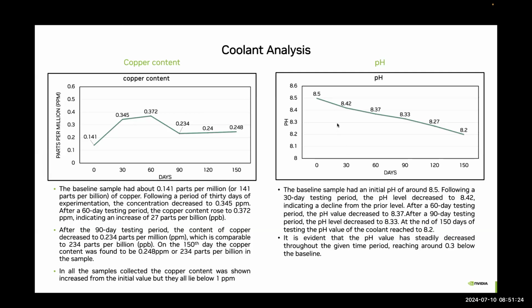It can, Phil. I think Dave is on the call too. This isn't atypical of what you'll see in a closed liquid cooled loop with copper cold plates. There's kind of like the 0.3, 0.2 ppm. That's kind of what we would see typically. Sometimes it's a little lower in the 0.1, 0.2 range.